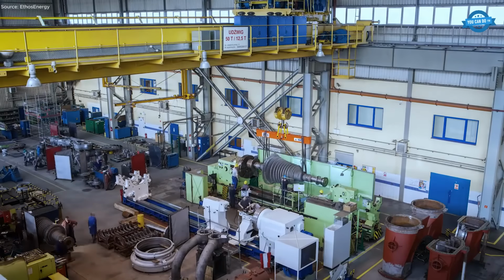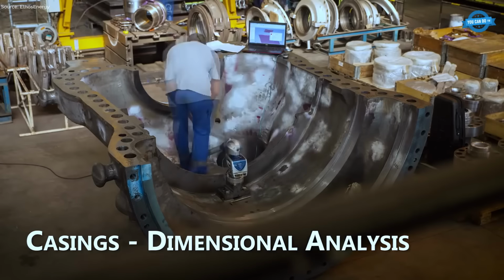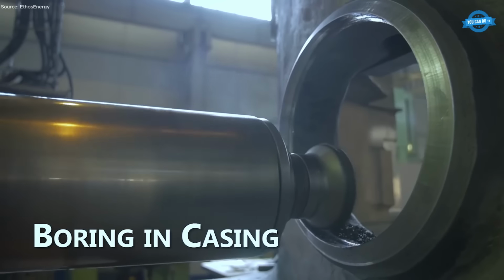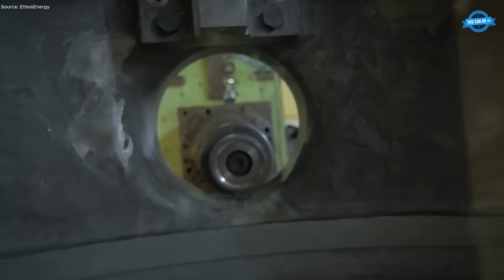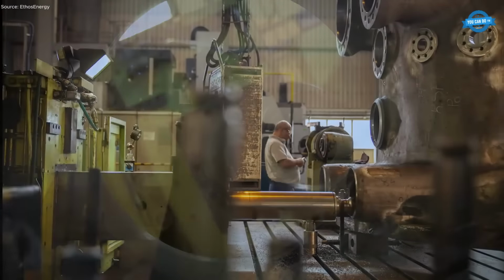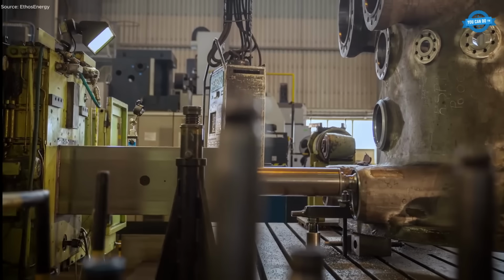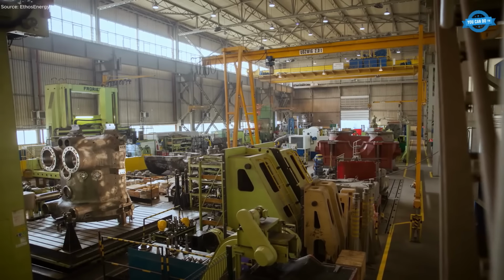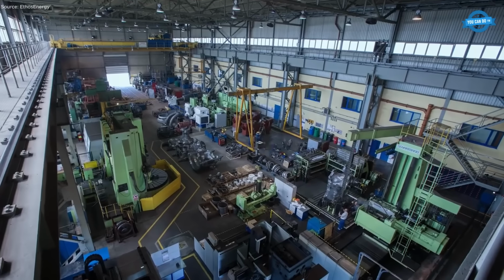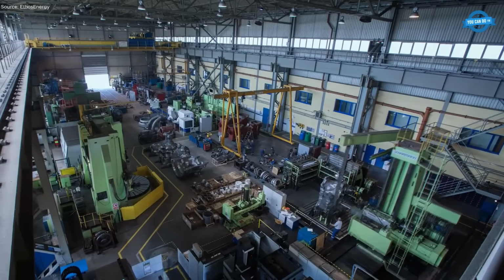For the turbine casings, a full dimensional analysis is performed, and boring operations are carried out to restore alignment and tolerances. Dynamic verification takes place in the high-speed balance bunker, using spare bearings and oil seals to replicate actual running conditions.